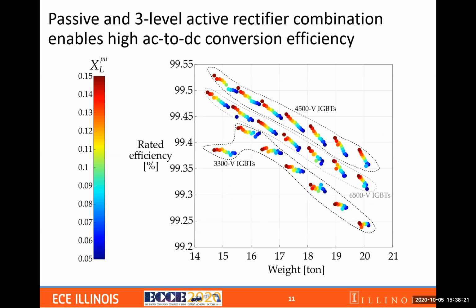From the power electronic perspective, we are trying a 3-level converter with 3 types of switches available at high power: 3.3 kV, 4.5 kV, and 6.5 kV. Why a 3-level converter? Because we found that this is the trend in the high power drive. A lot of companies are trying to push toward the 3-level converter because it can provide relatively high voltage capability, and it could have pretty good conversion efficiency as well. So you see there are 2 trends here. The first is that the conversion efficiency is dependent on the switch selection. For the switch, we consider the 4.5 kV IGBT provides the best conversion efficiency.